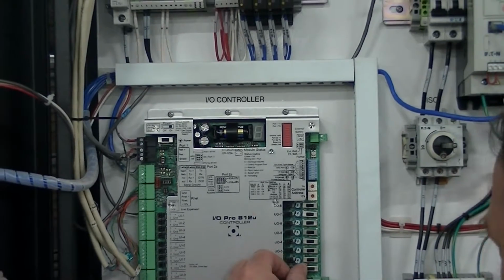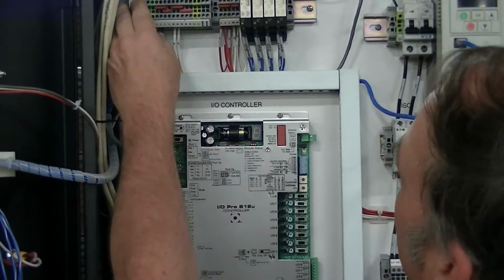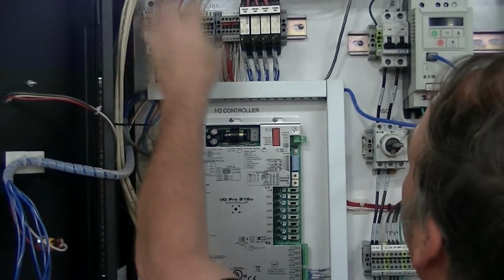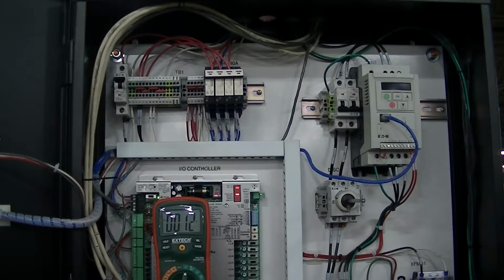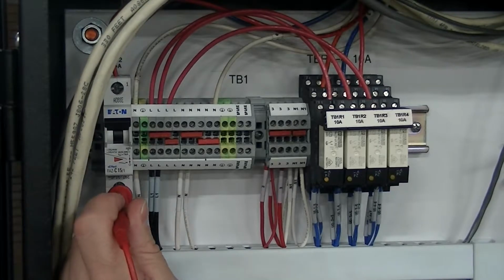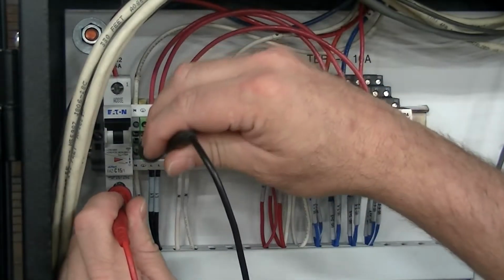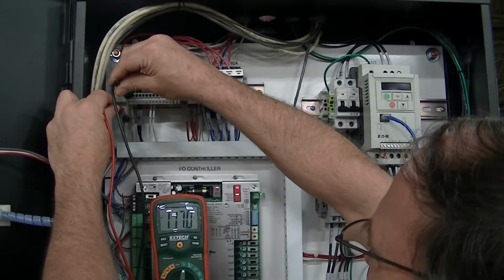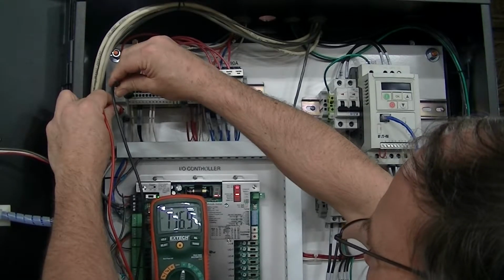When all the wiring in the control panel is in place and correct, you are ready to power up the control panel. Have the electrician turn on the breaker to the control panel. Test this by using a voltmeter, making sure you have 120 volts AC on the incoming terminals.